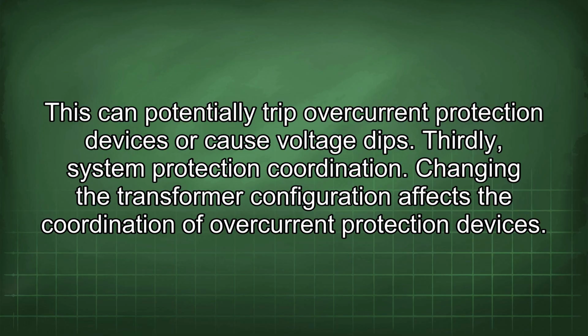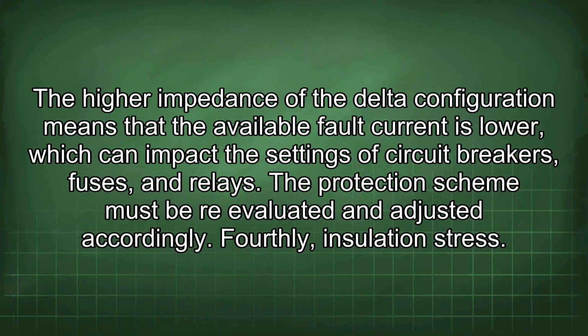Thirdly, system protection coordination. Changing the transformer configuration affects the coordination of overcurrent protection devices. The higher impedance of the delta configuration means that the available fault current is lower, which can impact the settings of circuit breakers, fuses, and relays. The protection scheme must be re-evaluated and adjusted accordingly.